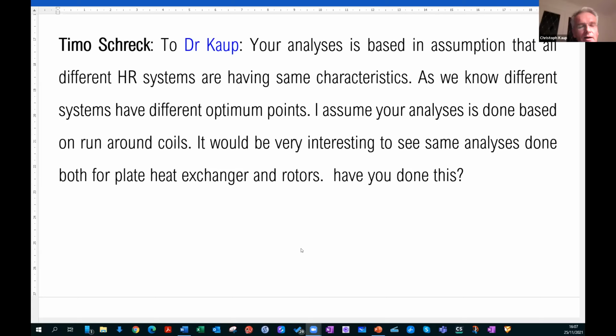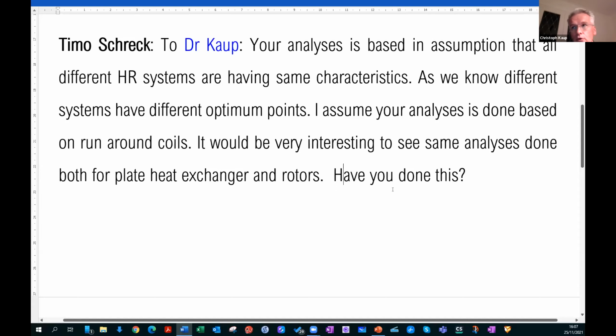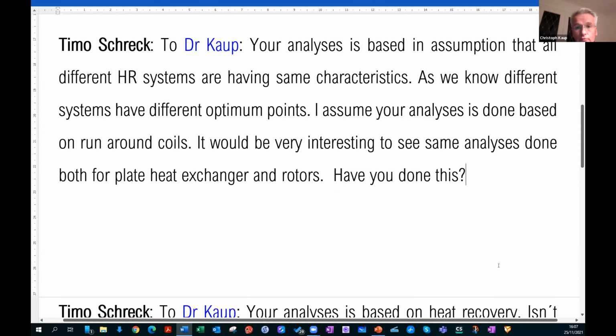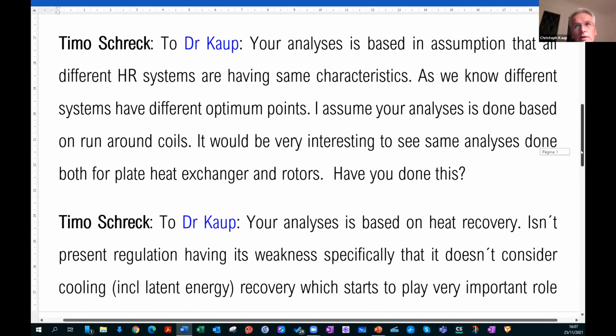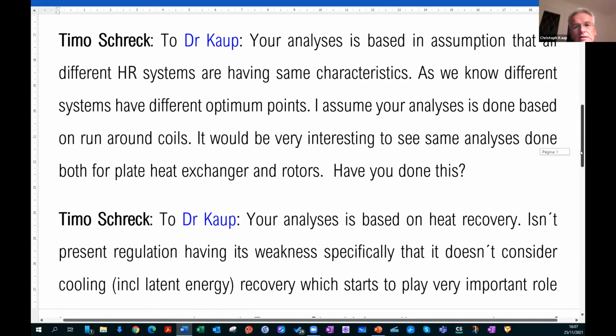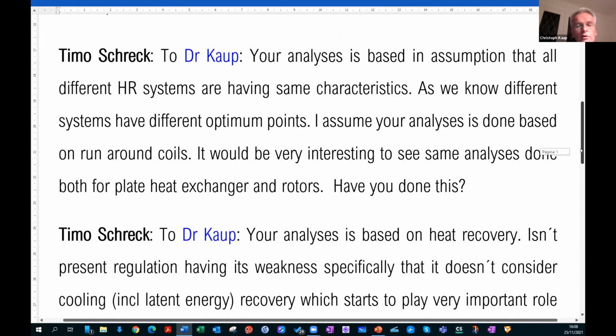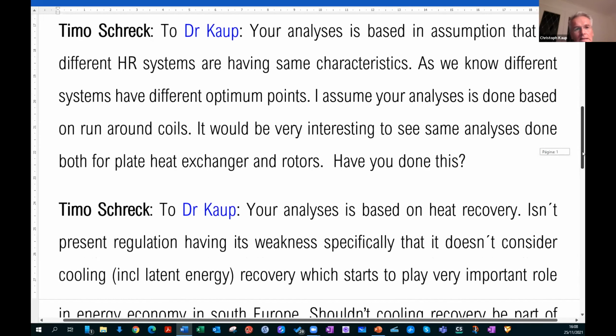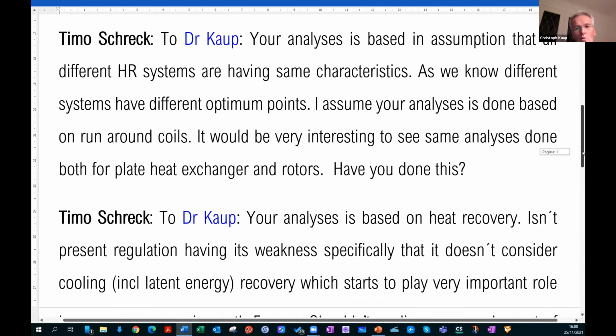Have you done this? At first, I have to say that this is not true. We made these calculations not only on run-around coils. We made those calculations, as I already showed in our study, with more than 3,000 units. We had there 50% plate exchangers, roughly 30% run-around coils, and 20% rotors. So we implemented all of them, and that's, I would say, an average of all. That's true, but for sure the difference between all these systems is mainly based on the pressure loss. But if we go down to lower air speeds, the pressure losses come closer together, because the impact of the pressure loss decreases with lower velocities.